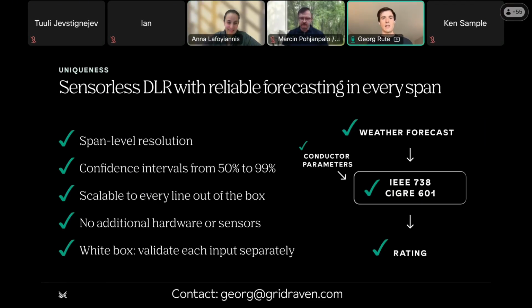This is the last slide, the summary of the solution we built. We have fixed weather forecast in the sense that we have span level resolution accounting for the detailed terrain around that span, and we give confidence intervals to every weather input. So when the line ratings are provided based on the thermal balance equations with the conductor parameters, you're aware of the limitations of those equations, and you know the errors in the potential conductor parameters, spans, and thermal limits. You're able to see and verify every step of the inputs that go into the rating, and have ratings you can rely on and forecast multiple days into the future.